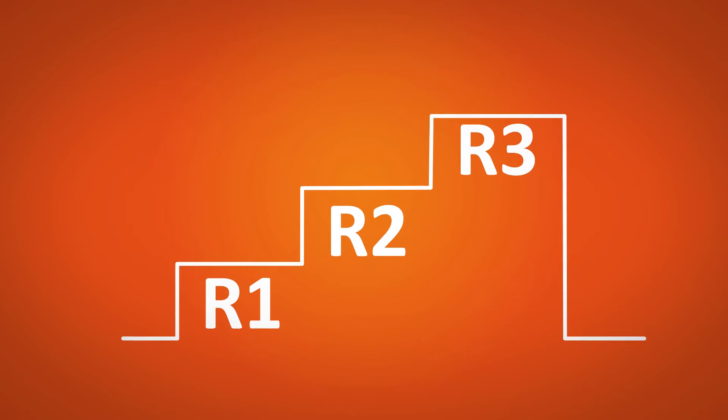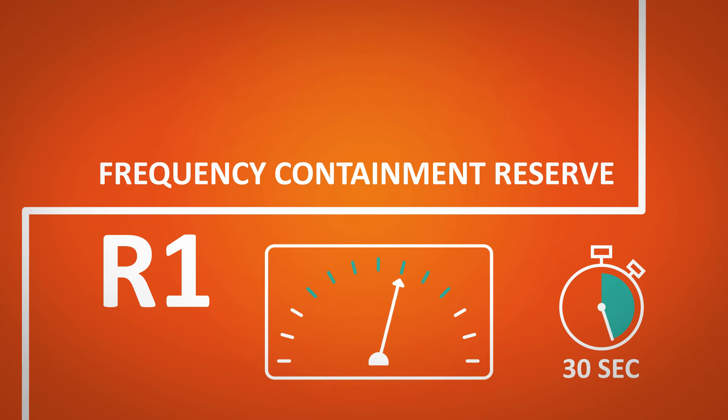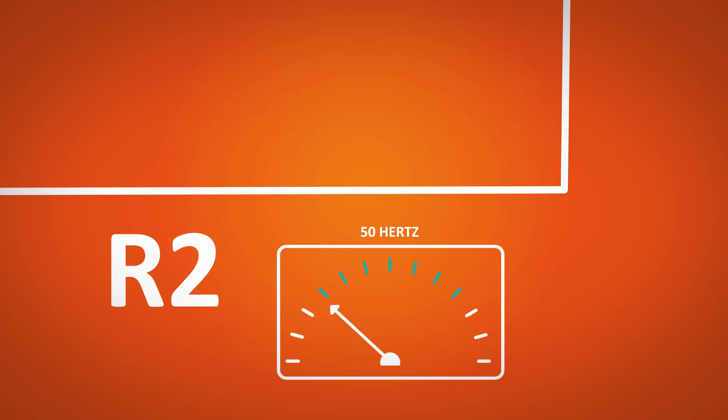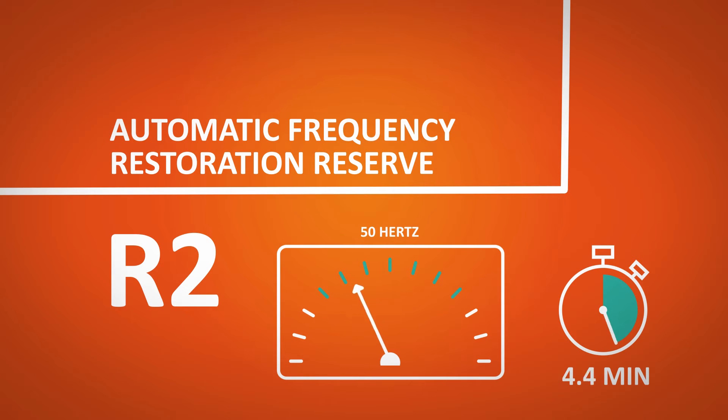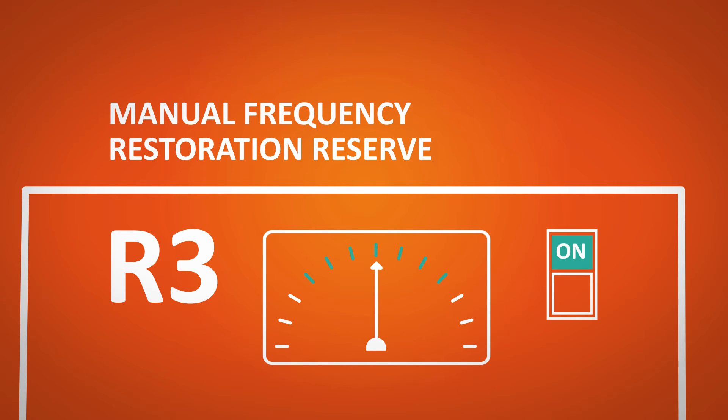Balancing the grid works in three escalating steps. In case of a frequency deviation, within 30 seconds, the frequency containment reserve triggers automatically. To restore the frequency to 50 Hz and rebalance the Belgian control area, the automatic frequency restoration reserve responds within 7.5 minutes. Finally, to address a major imbalance, Elia requests the activation of the manual frequency restoration reserve.